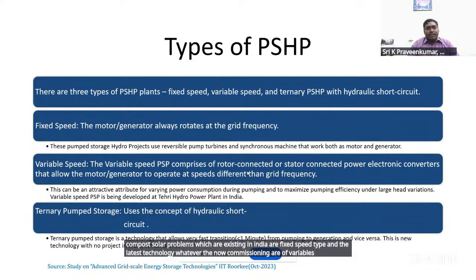The variable speed PSPs comprise a rotor connected or stator-connected power electronic converters that allow the motor and generator to operate at a speed different from the grid speed. With this, we can achieve 50% to 100% variation in input power by varying the frequency using converters.